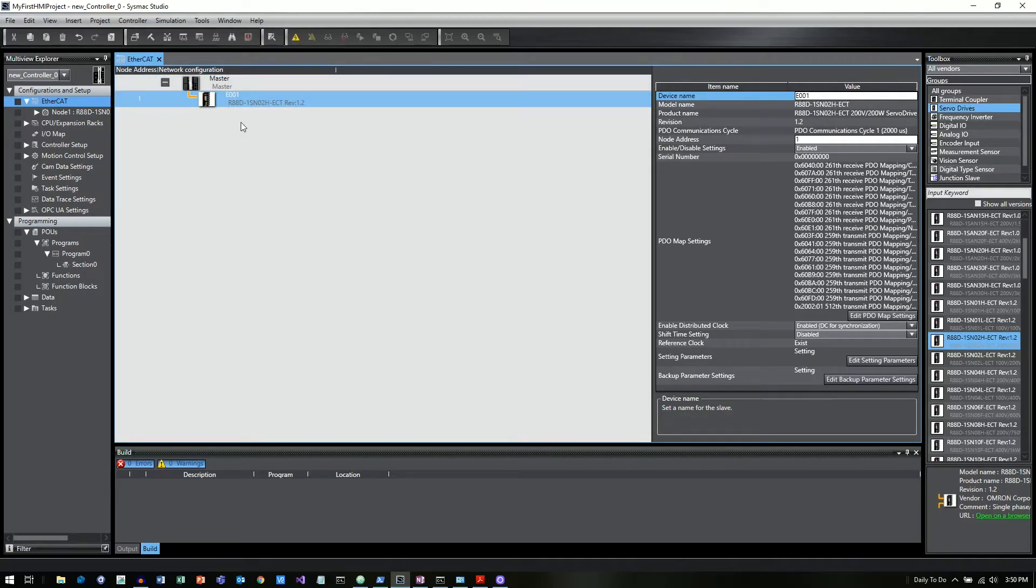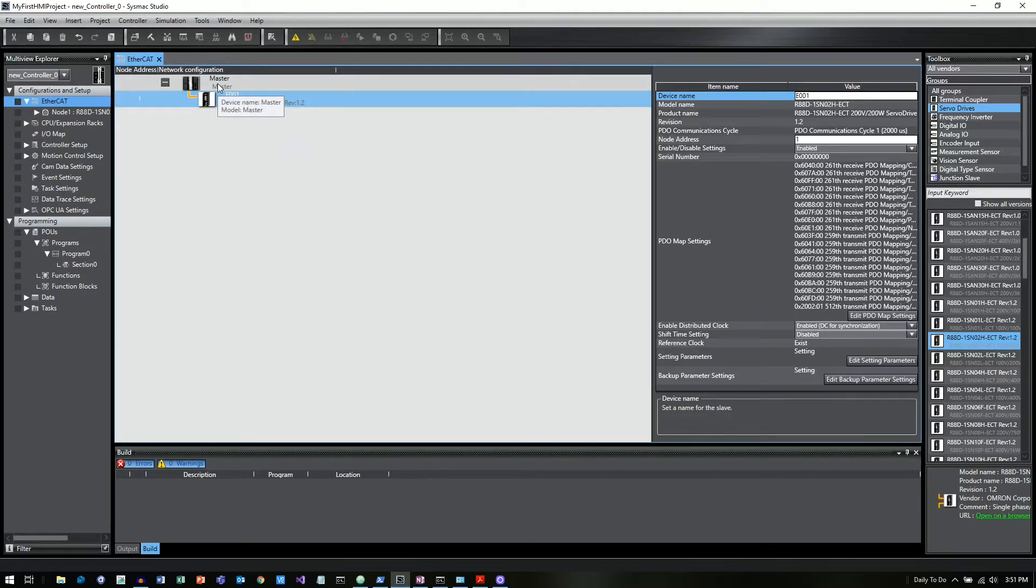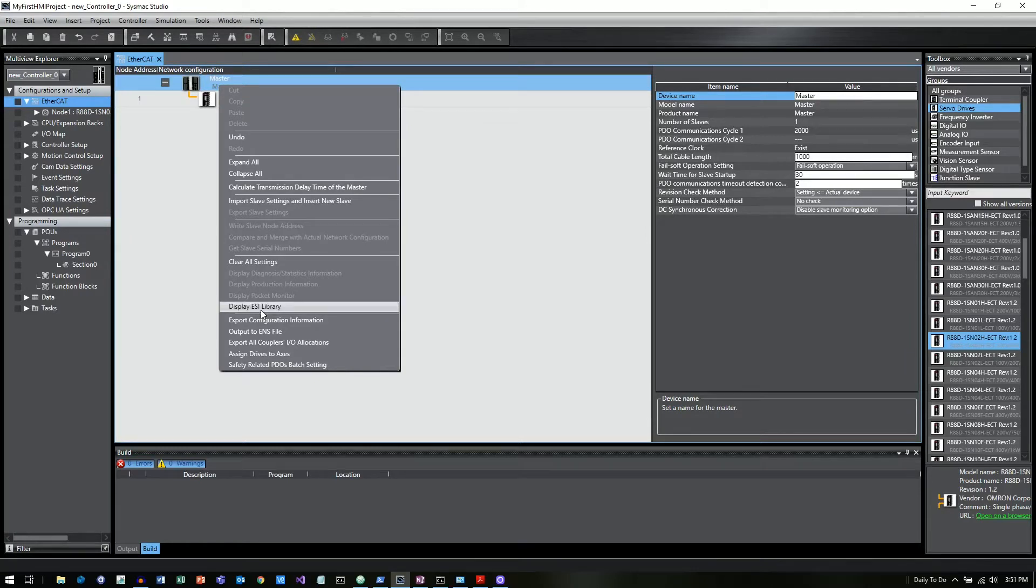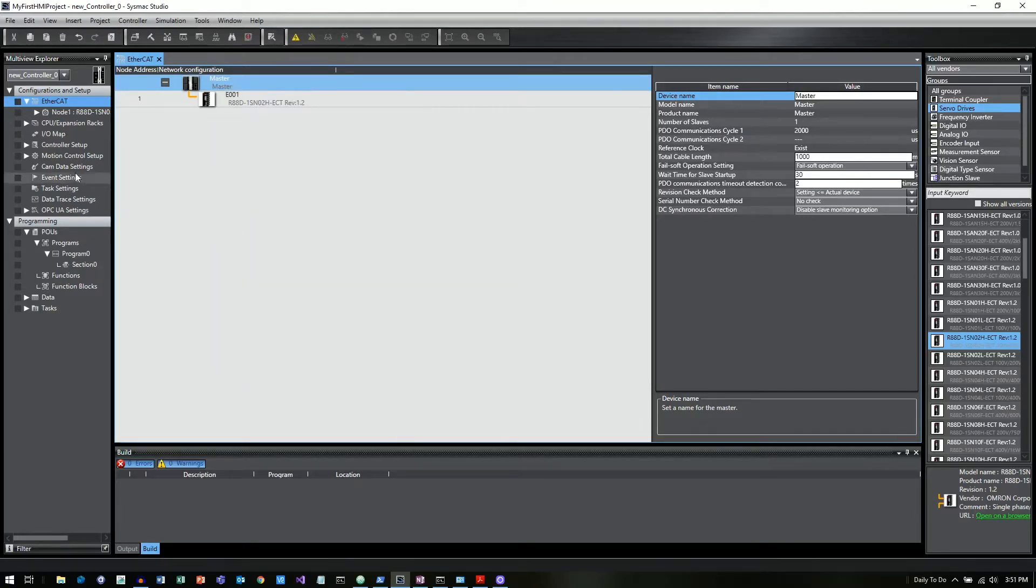I'm just going to grab and drag and drop that onto my EtherCAT tree and now that node is on there. If you were doing that live and in person, the other thing you could do if you were connected to a controller is you could right click on the master and then you would have this option here, which is grayed out for me right now, but is compare and merge with actual network configuration. And then that will actually pull in whatever is physically connected to your controller if you're online.